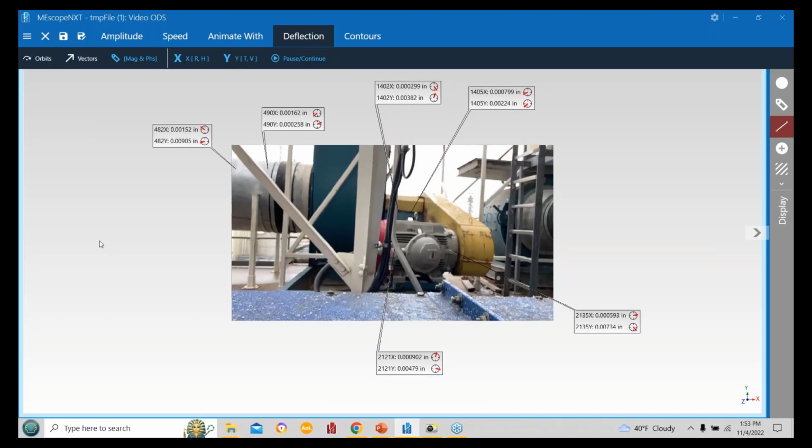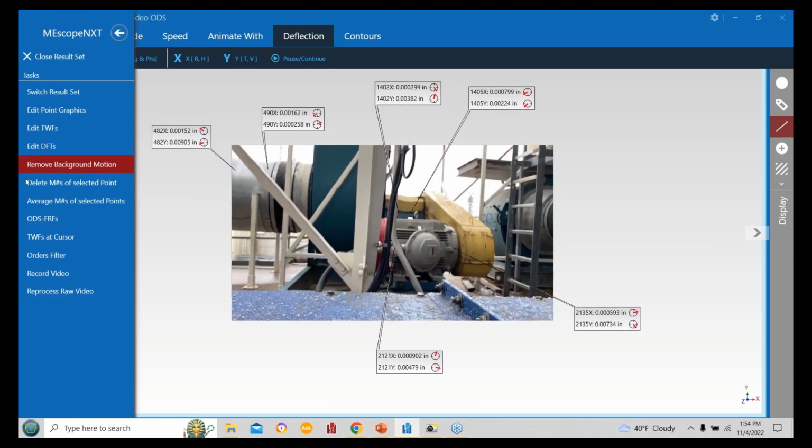Did you get any questions yet, Mark? First question here from Marion. Suppose you have a very high background spot. Should you remove the measurement point rather than average, right? Basically, it depends. If, let's say on my screen here, there was a really high spot on this deck that's hanging out nowhere, with nothing to do with this fan, you should definitely try to get rid of it. Actually, if it's really big, it might mess up the average that we were talking about before. In that case, you'd probably use this one.